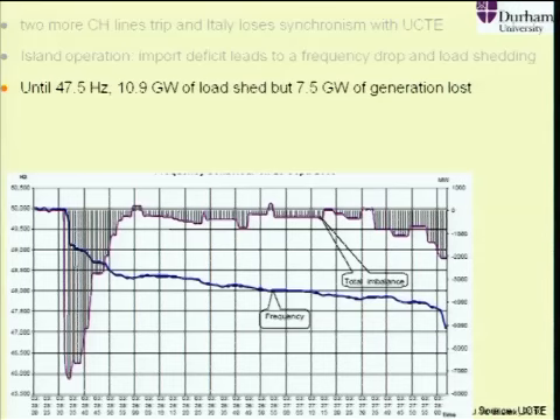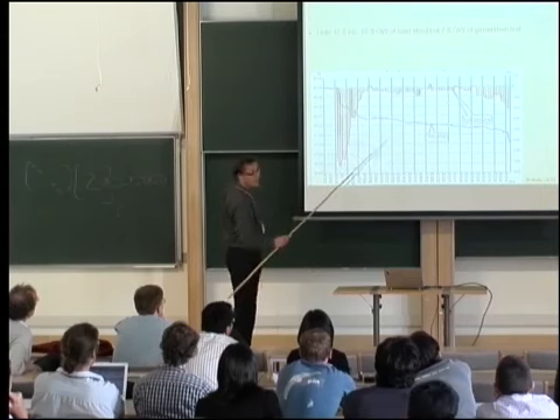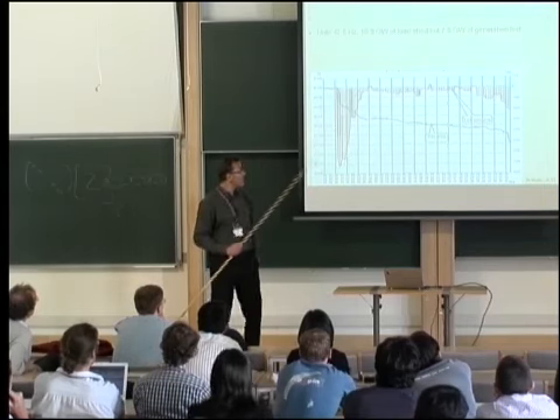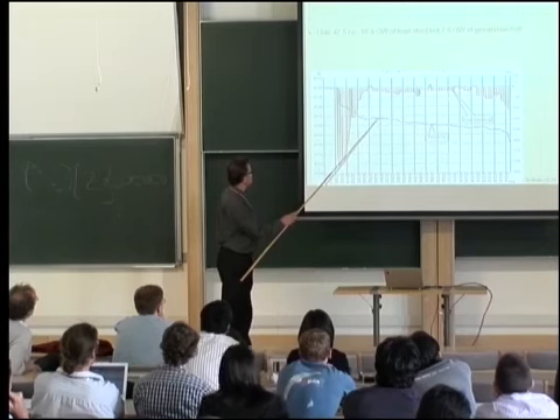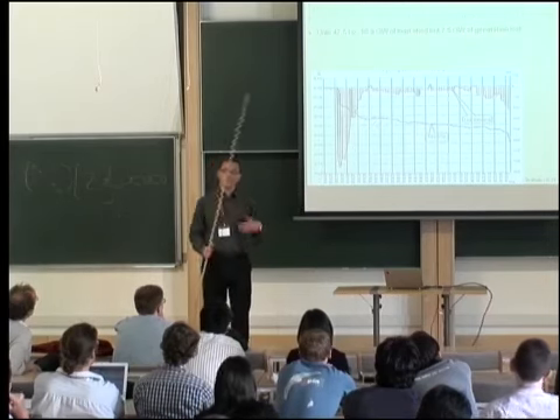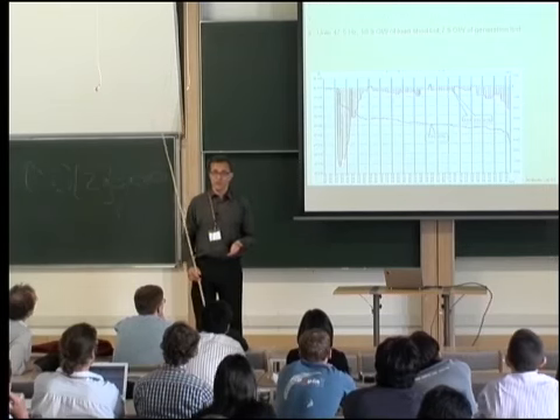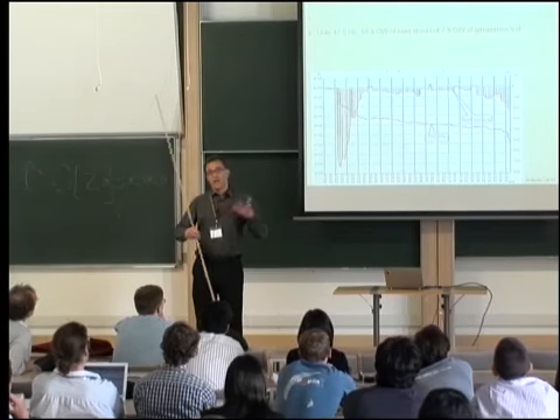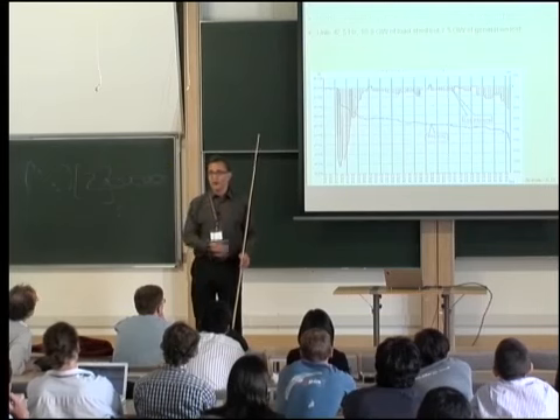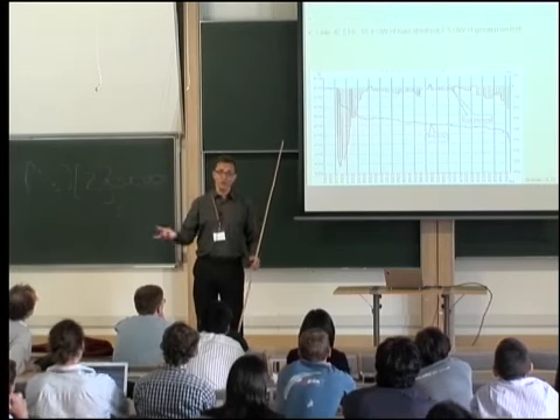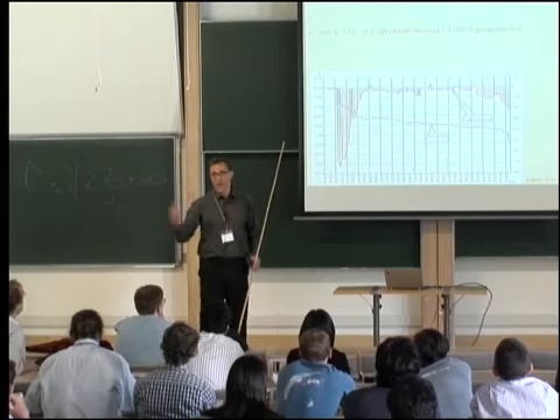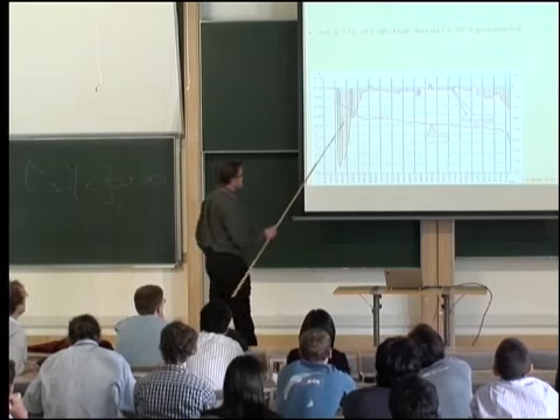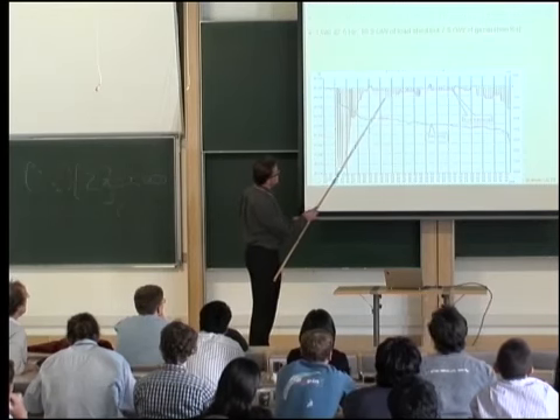However, because of the dynamics of the problem, and because the frequency was already pretty low, below 48.5 hertz, they started to lose traditional power stations. Every power station has different pumps that depend on frequency, and if frequency is too low, the pumps drop out—giving you a positive feedback mechanism. So as you can see, they started to lose even more generation.